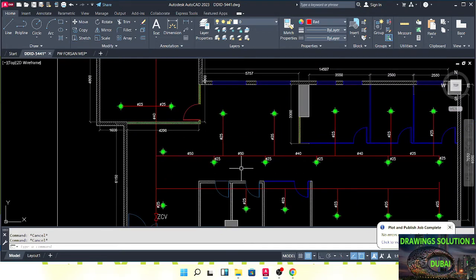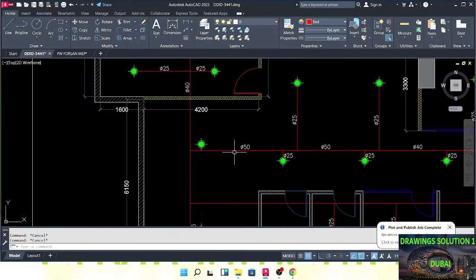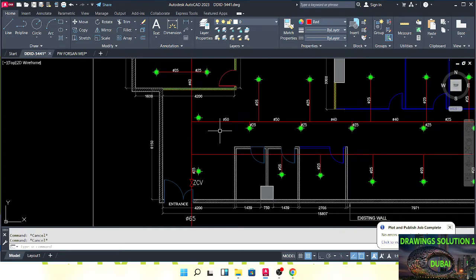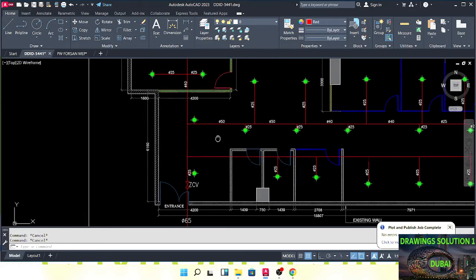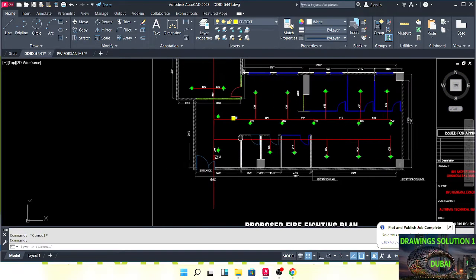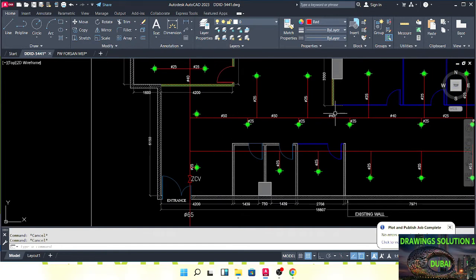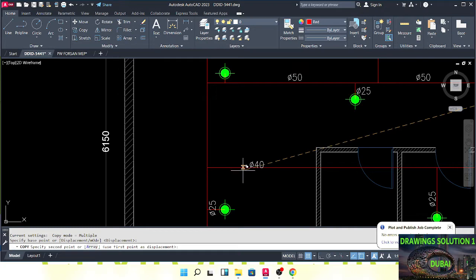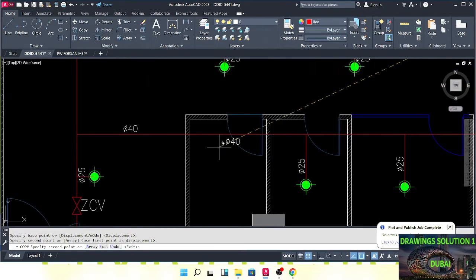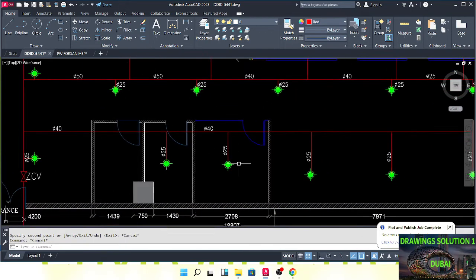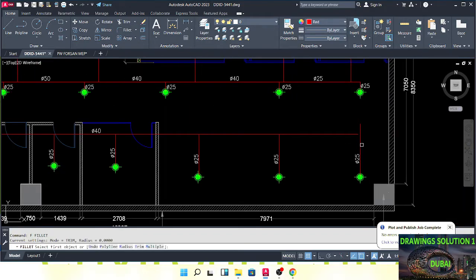This pipe is serving 10 sprinklers. If you have 10 sprinklers you have to use 50mm dia. If you have more than 10 then you go to the next size. Here we are serving only 5 sprinklers, so use 40mm dia. This is as per DCD — not my will, this is the DCD requirement.